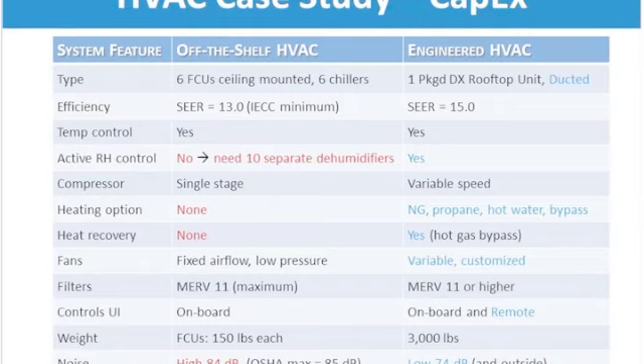It's going to respond smoothly between those changes. There's no heating option on the off-the-shelf system. With engineered, it might just be electric, done, or with the engineered system you might have options with electric, natural gas, propane, hot water coils, or diesel in some cases. The off-the-shelf system doesn't have heat recovery, but the engineered does, and that's probably why it has a higher efficiency rating. We're not talking a lot about fans and airflow today, but there might be benefit to having variable speed fans in your HVAC system. We can have filters in both, and controls, onboard versus remote.